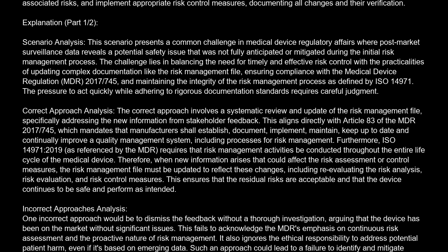Incorrect approaches analysis. One incorrect approach would be to dismiss the feedback without a thorough investigation, arguing that the device has been on the market without significant issues. This fails to acknowledge the MDR's emphasis on continuous risk assessment and the proactive nature of risk management. It also ignores the ethical responsibility to address potential patient harm, even if it's based on emerging data. Such an approach could lead to a failure to identify and mitigate emerging risks, potentially resulting in patient harm and noncompliance with Article 83 of the MDR.